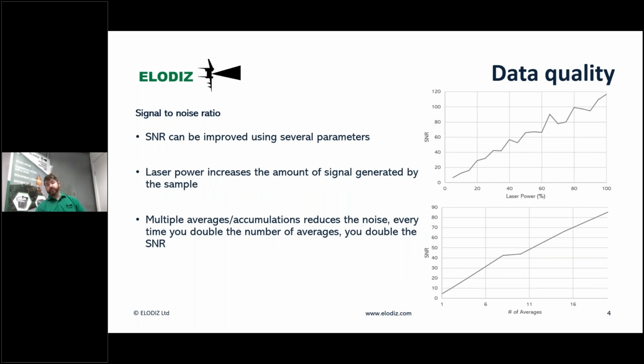So you can improve your signal to noise by possibly increasing your laser power if it's safe to do so with your sample, or by taking averages of multiple spectra, which some systems allow innately, while other systems you might have to do this manually, taking multiple averages or accumulations, and this will reduce the noise. Essentially, you will double your signal to noise ratio as you double the number of averages. Eventually there gets a point where you have to make a judgment on whether you are taking longer to do an experiment to get very good data, or if slightly shorter times will give you satisfactory data.